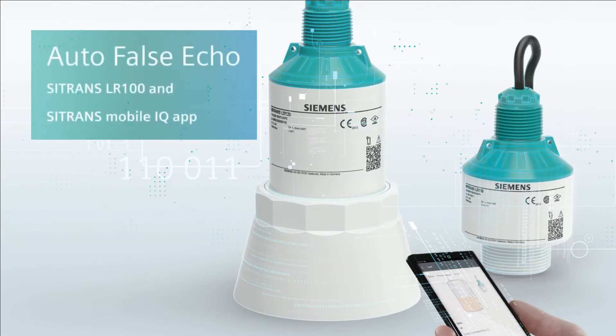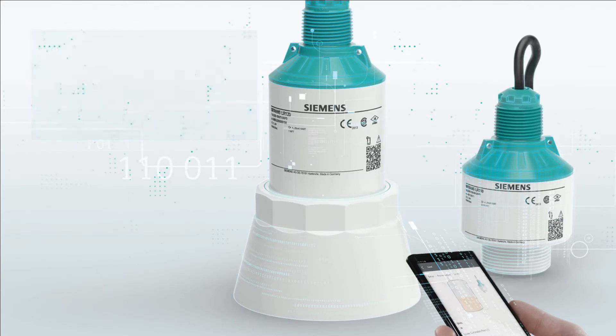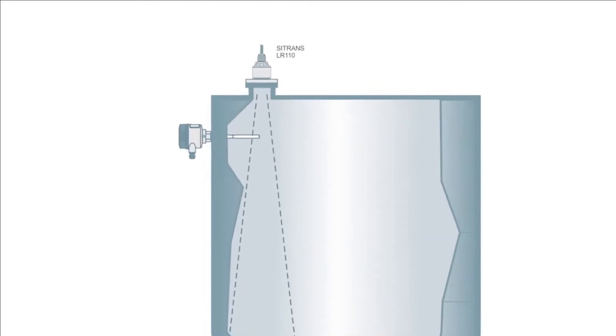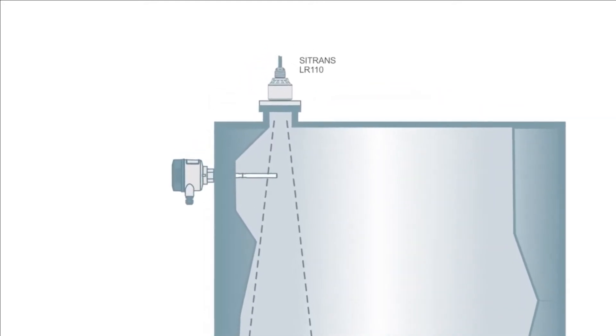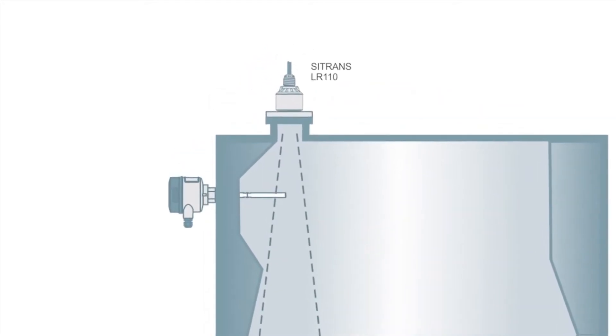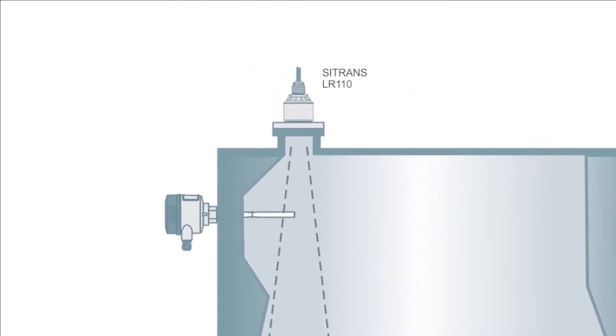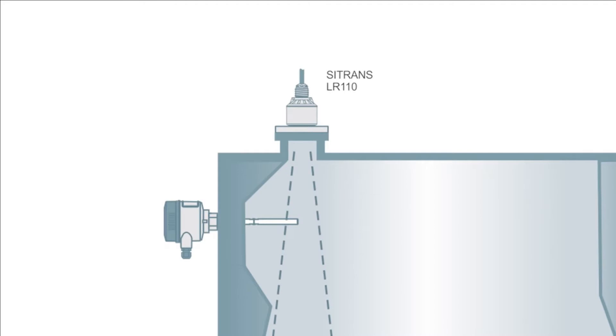Sometimes we cannot avoid fixed false targets within the application. In this example, we have a high-level switch which is interfering with the main beam of the continuous level radar sensor.